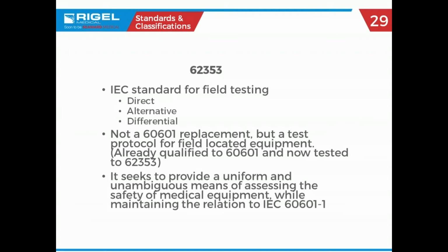So for the 62353, all three of those criteria have to be checked? No, you can select whether you want to do direct testing, which is what we're going to do up here. You can select whether you want to do a differential test, which is just you have two current transformers on the main voltage coming in. So whatever is going in and is not coming back out is going somewhere. It's leakage. So you pick which one of those you want to do. Again, dialysis guys, they love differential. It's fast, simple, easy. And a lot of dialysis machines specify 62353 for the manufacturer's specification and how to test.